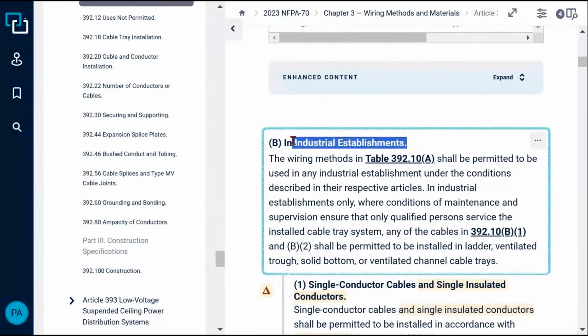Industrial establishments. Who determines the industrial establishment? That's going to be the AHJ - something you need to work with the locality on, because that's typically not going to be just a regular commercial environment. It's industrial, producing products, those type of things. People don't understand that; they think you can just put regular single insulated conductors in cable trays all the time. That is not true - it has to be an industrial establishment.